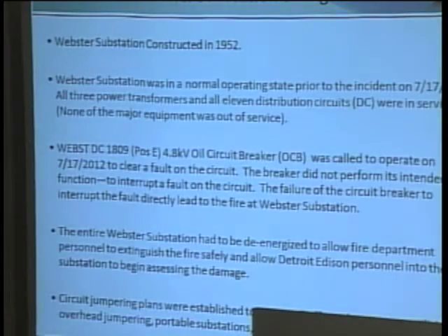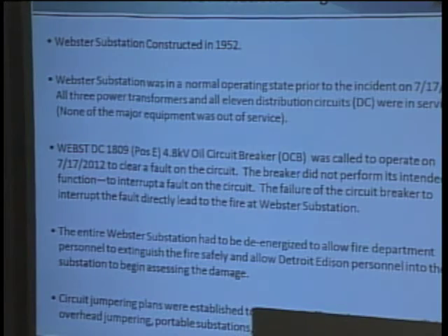Now, the intent of this is to go through what caused the major problems back on July 17th. But to go through, originally, Webster Substation, the substations were constructed in 1952. It seems like that is an older substation, but with most equipment, what we do is we update it as time and maintenance is required. And we also improve or add distribution circuits, change the relaying and other improvements as they become available in all of our substation areas due to preventive maintenance.